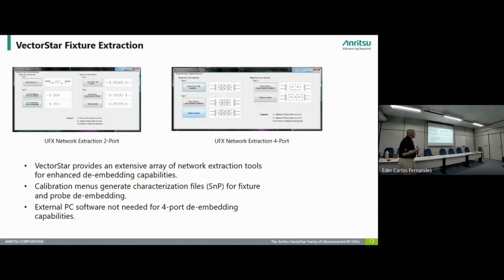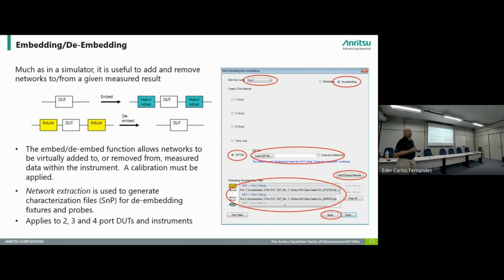Once we've got the file, we go into our embedding, de-embedding menu, and we apply it to the correct port, whatever it is we want to de-embed. We load the file, drop it down in there, and apply it. Now we've moved our reference plane to where the device is that we want to measure. But as I said before, network extraction is required to get to this point. We can't de-embed until we have the actual file, and then we can de-embed it. So that's how de-embedding works. It relies on that S4P file that you get through network extraction.